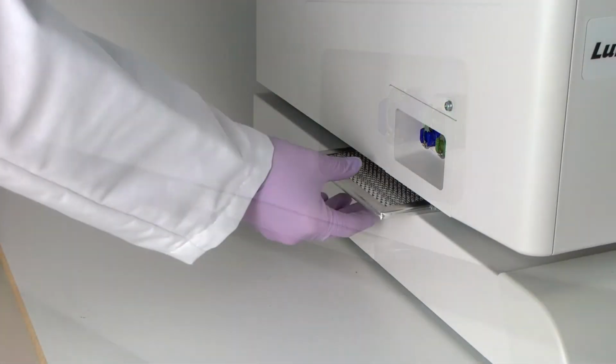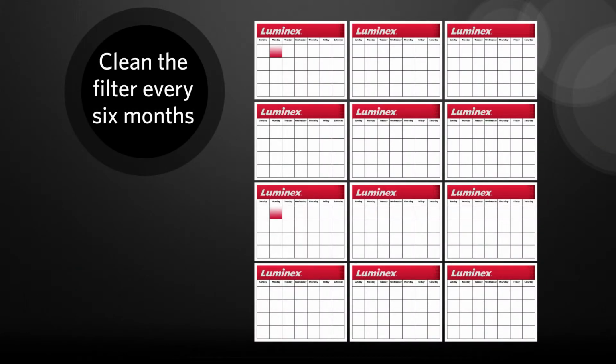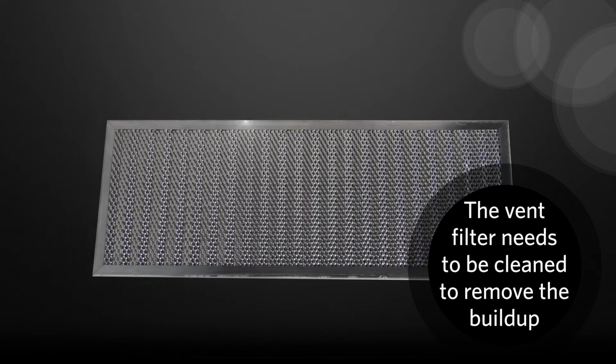And finally, remember, cleaning the vent filter on the Luminex 200 analyzer needs to be completed every 6 months. This filter keeps dust and debris out of the instrument. The filter needs to be cleaned to remove the buildup.